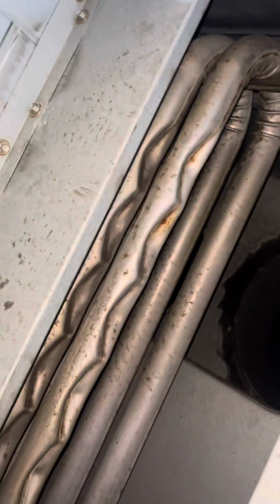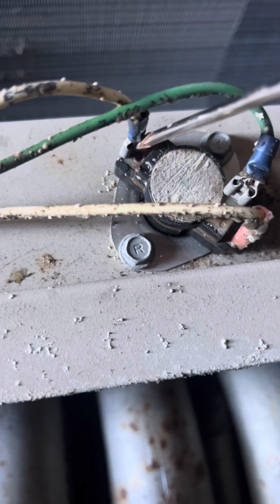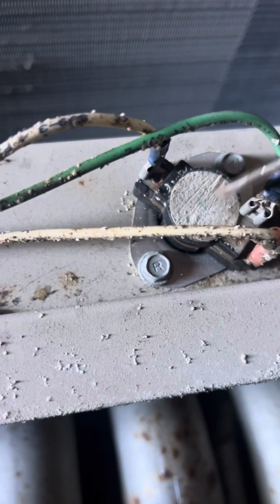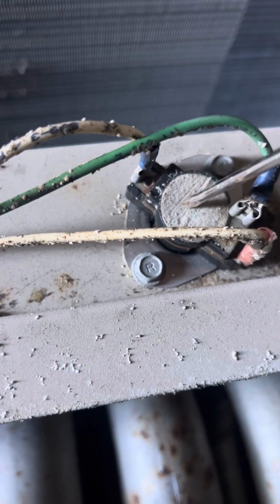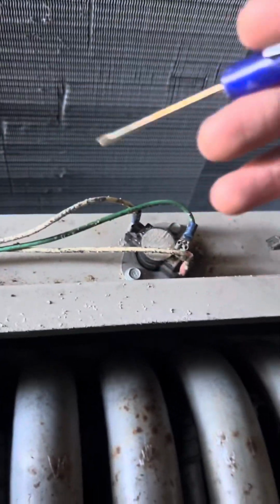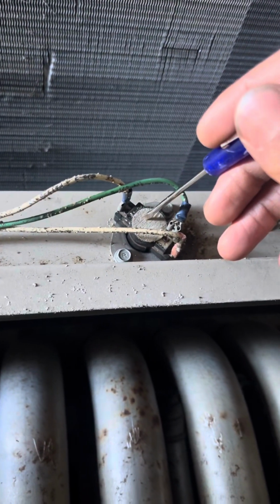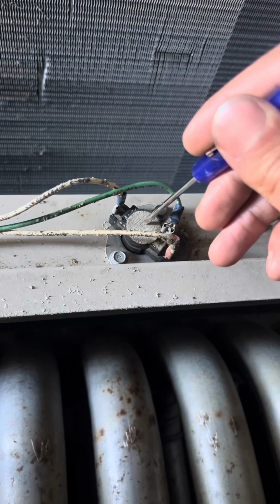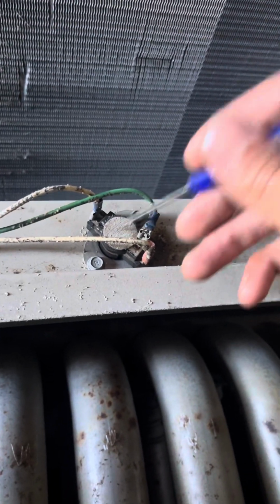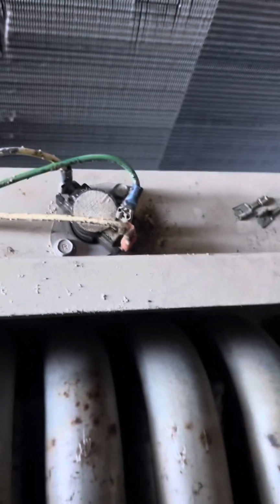But yeah, the limit switches just look like some shit - limit switch for stage 1, limit switch for stage 2. They're supposed to be closed at all times unless the temperature gets too high inside here, whether it's because the blower's not running, filter's dirty, whatever reason - it's a safety for the unit. So I'm gonna check the integrity of these. I'm still gonna jump them out. I mean, you'd rather have all your safeties in good shape.